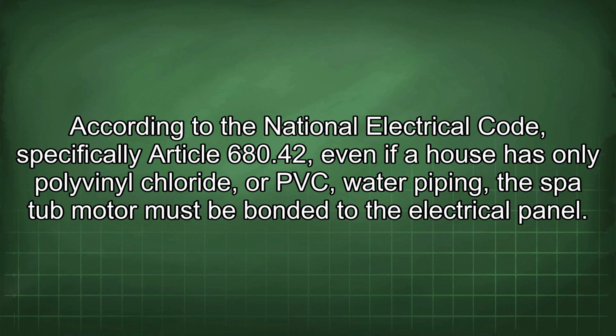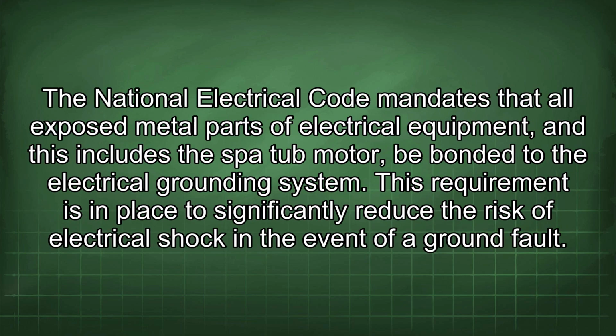According to the National Electrical Code, specifically Article 680.42, even if a house has only polyvinyl chloride, or PVC, water piping, the spa tub motor must be bonded to the electrical panel. The National Electrical Code mandates that all exposed metal parts of electrical equipment, and this includes the spa tub motor, be bonded to the electrical grounding system. This requirement is in place to significantly reduce the risk of electrical shock in the event of a ground fault.